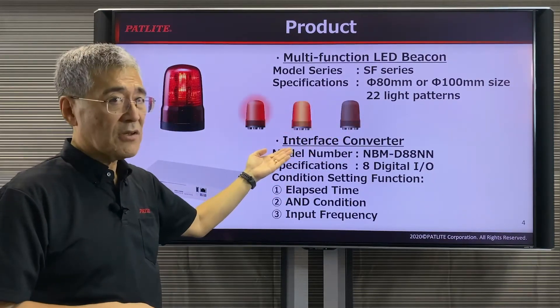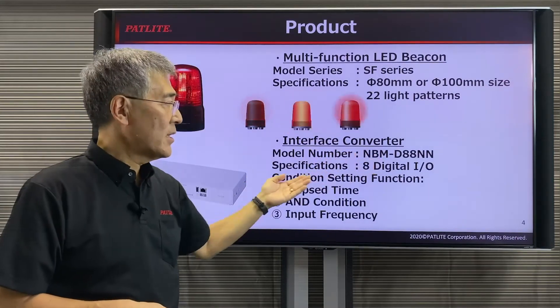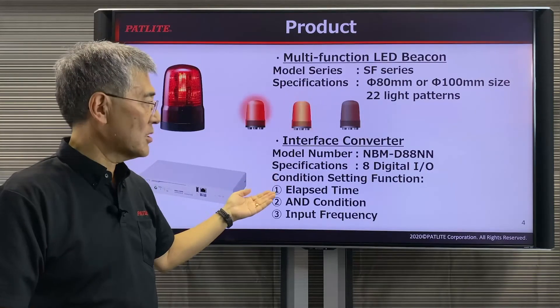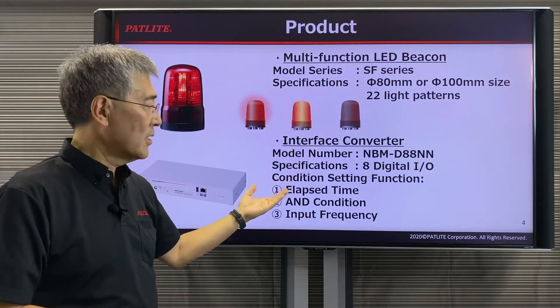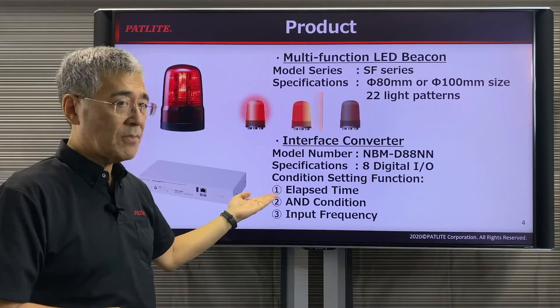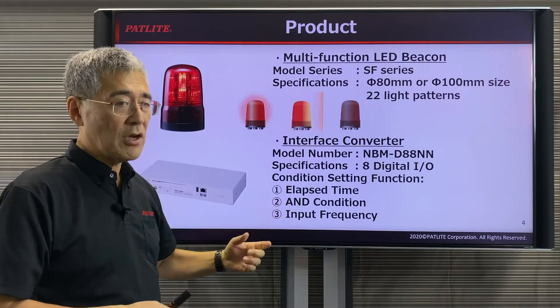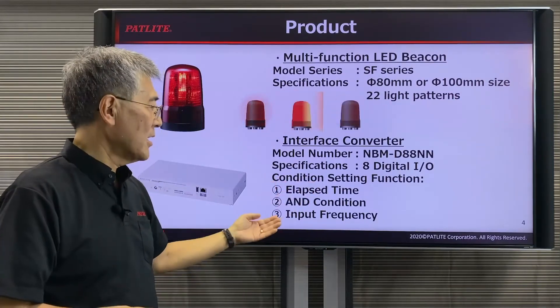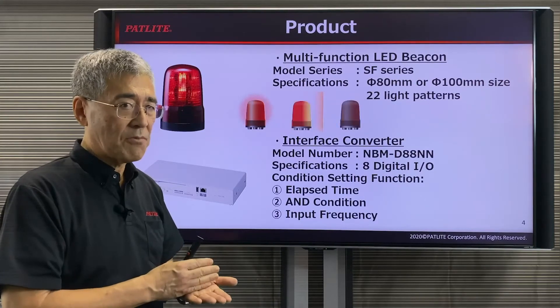The interface converter is the NBM D88NN. It has 8 digital inputs and outputs and has a condition setting function. With this function, you could set triggers based on elapsed time. This AND condition allows you to have multiple inputs before a trigger happens, and the input frequency depends on how often something happens.